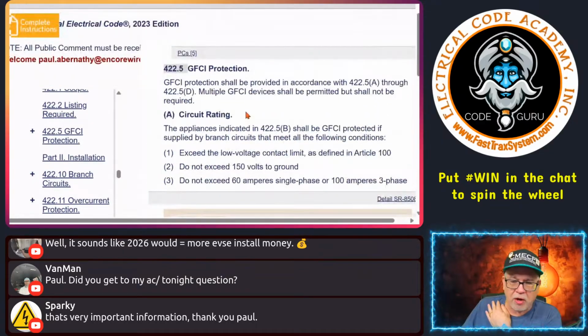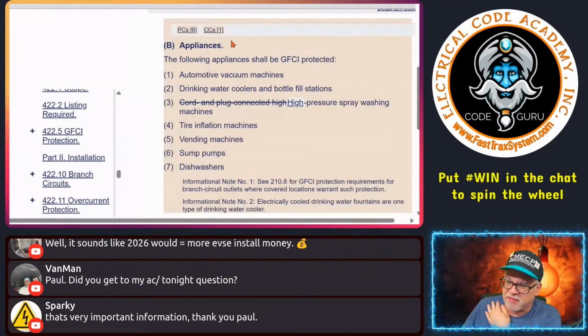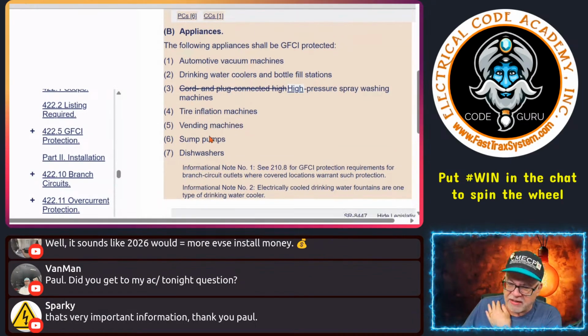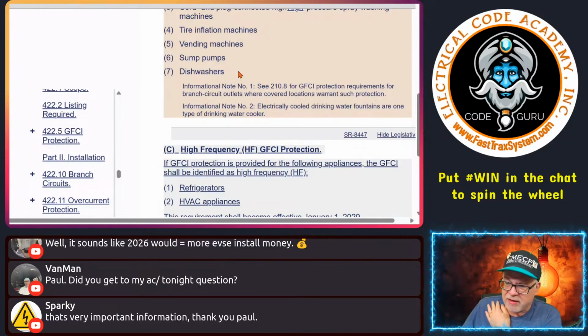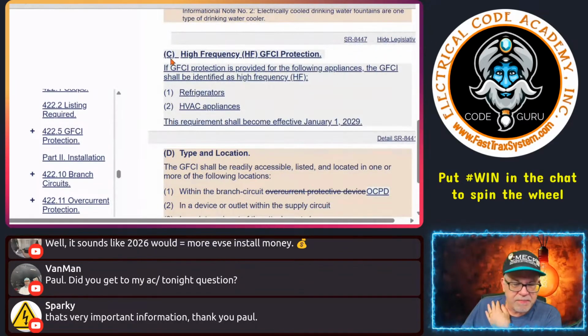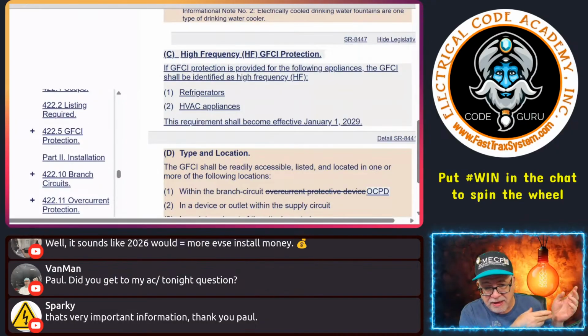All right, so here's what we did, this is what Code Panel 17 did. See, here's the appliances, right? Notice what the list is, it doesn't have those other things on it. However, we added a C, and the C allows for this high-frequency HF GFCI protection that the manufacturers say they have, but it's not going to become effective till January 1st, 2029, so we're giving them time. But it only applies to HVAC appliances, which is going to be a conflict, really, on what we did back in 210.8F.